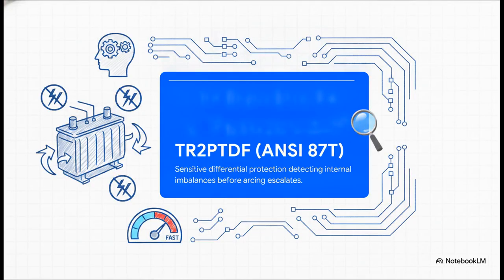And that brings us to the real hero of the story here, TR2P-TDF, the highly sensitive differential protection stage, also known as ANSI 87T. We've talked about this function before with generator transformer blocks, but here it's applied to standalone stationary power transformers. Since the only fault-feeding source now is the connected network, this stage is designed to act as a high-speed intervention.